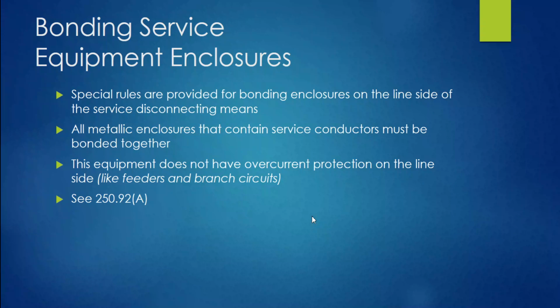All right, let's talk about bonding service equipment enclosures now. There are special rules that provide for bonding enclosures on the line side or supply side of the service disconnection means. We're talking about on the line, not on the load side of the service disconnection means. Okay, all the stuff we've been talking about for supply side bonding jumpers takes place on the line side. Now, all metallic enclosures that contain service conductors must be bonded together. We've established that in 250.92A, which we're going to look at the code here in a second.